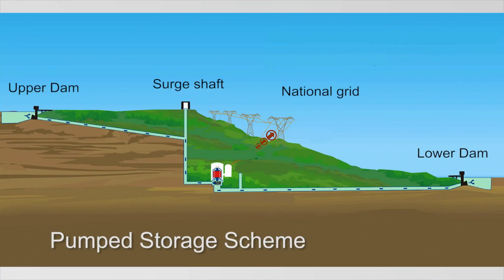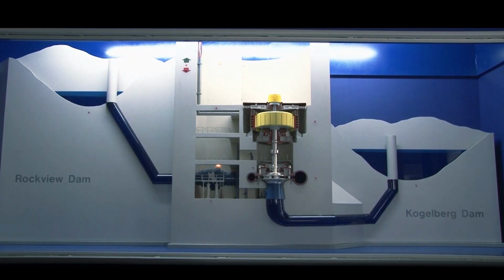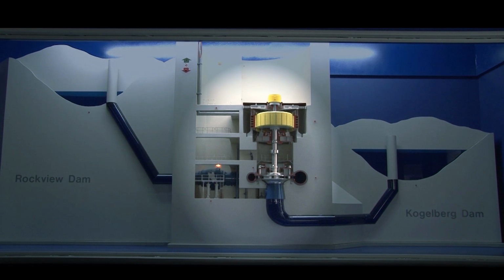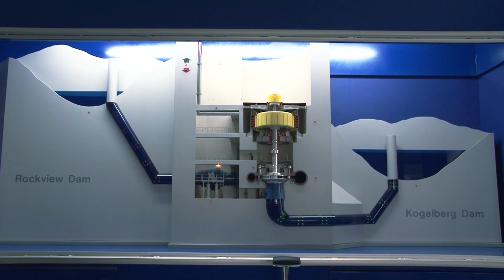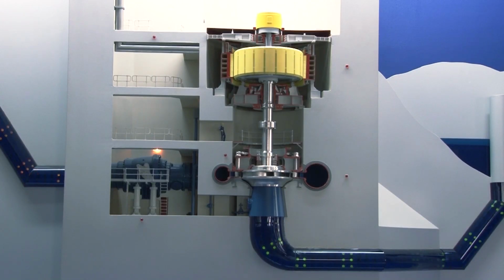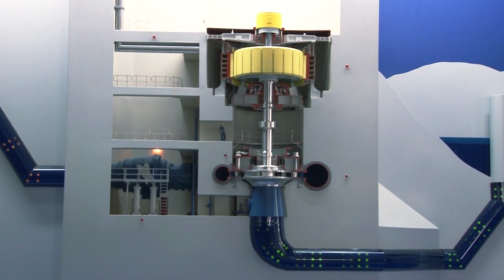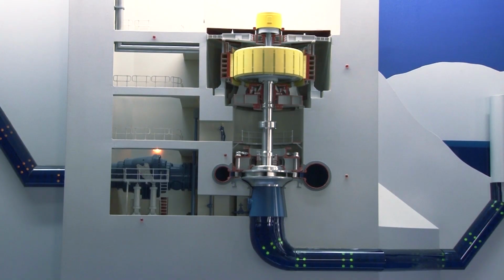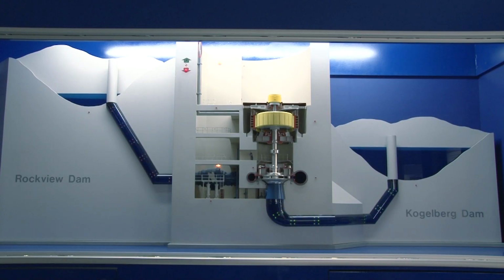A pumped storage scheme consists of a lower and an upper dam. Between these two dams, a power station, which also doubles as a pumping plant, is located. During periods of emergency or peak demand, the water stored in the upper dam is released into large waterways to flow through the turbines to generate electricity. During off-peak periods when customers' demand for electricity has decreased, the reversible pump turbines use electricity from the grid to pump the water back up to the upper dam.